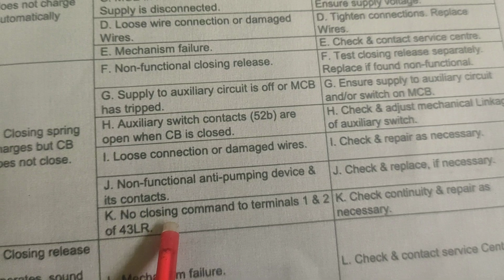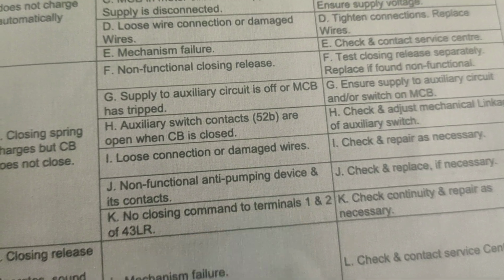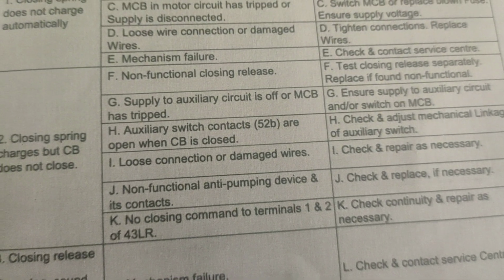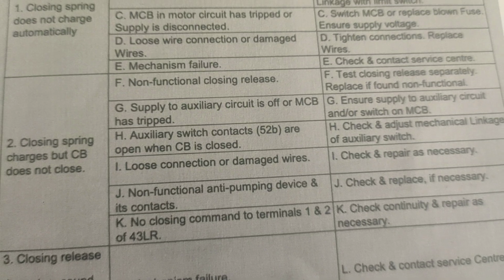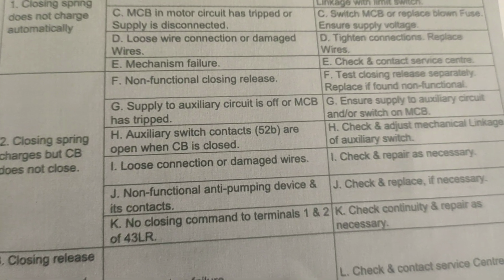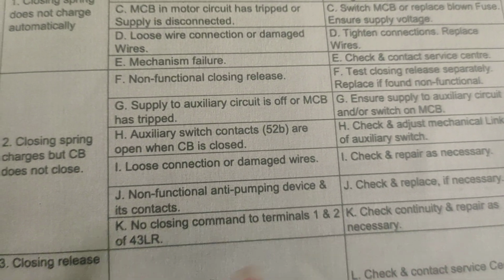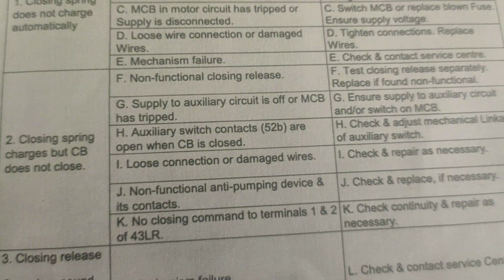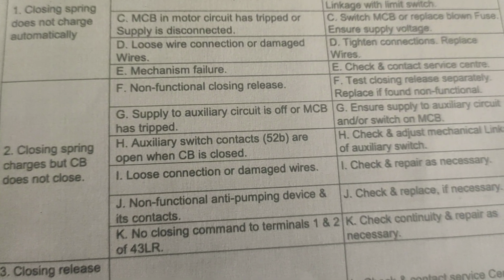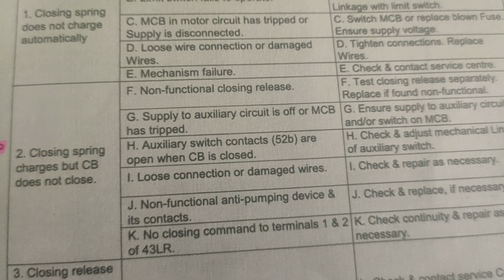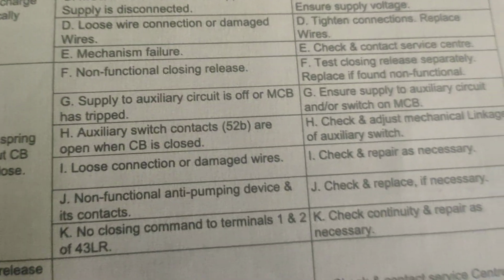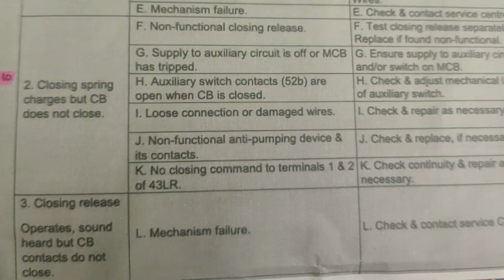The non-closing command to terminals 1 and 2 of the 43LR. 43LR is the local and remote switch. So local and remote switch problems may be there. If there is a local remote problem, you cannot easily close the circuit breaker. So check the continuity and repair as necessary.